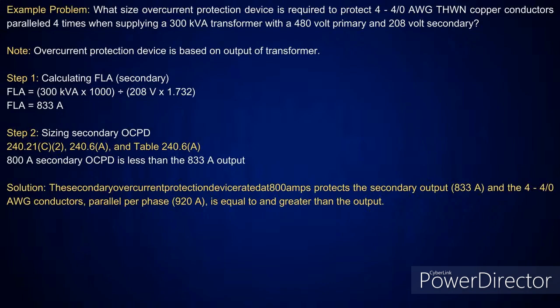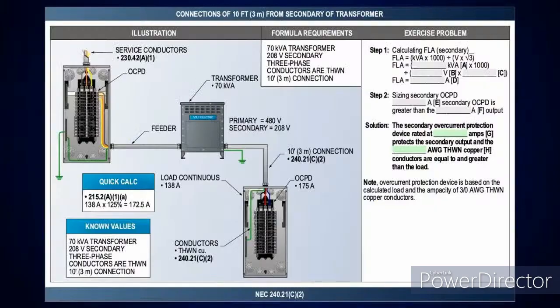Now, I could say I need an 800 amp overcurrent device there, but if I actually do the calculation, with four 4/0 conductors at 230 amps per conductor, that's going to give me 920 amps. I could actually go to a 900 amp device. But that's a custom size. It's not a standard size per Table 240.6(A), but you can purchase them.